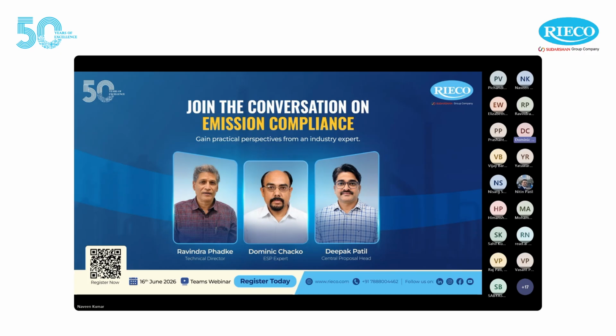And the second aspect I would like to talk about is the electricals. Very often, the general perception is that the more power you pump into any ESP, that is, increase the voltage, increase the current, the better performance you are likely to get. That also need not be true in many cases, because in most of the large power plants in India, you have a problem of highly resistive coal. The coal that is being used is highly resistive, so that when it is fired and passed through the ESP, you encounter the problem of what is known as back corona.